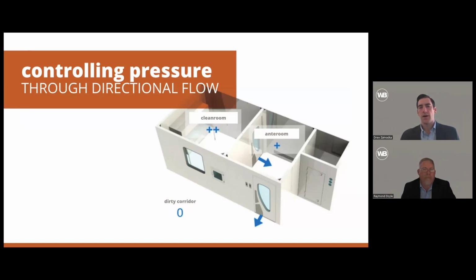So now that we talked about how to filter the air and how air moves through the space, the next thing in design is controlling the pressure. So utilizing pressure differentials will help control contaminants flowing into your clean room. You would do this by pressurizing one room via a volumetric offset to the adjacent rooms, and then maintaining a differential pressure across the door. And this is all designed in a closed door arrangement.